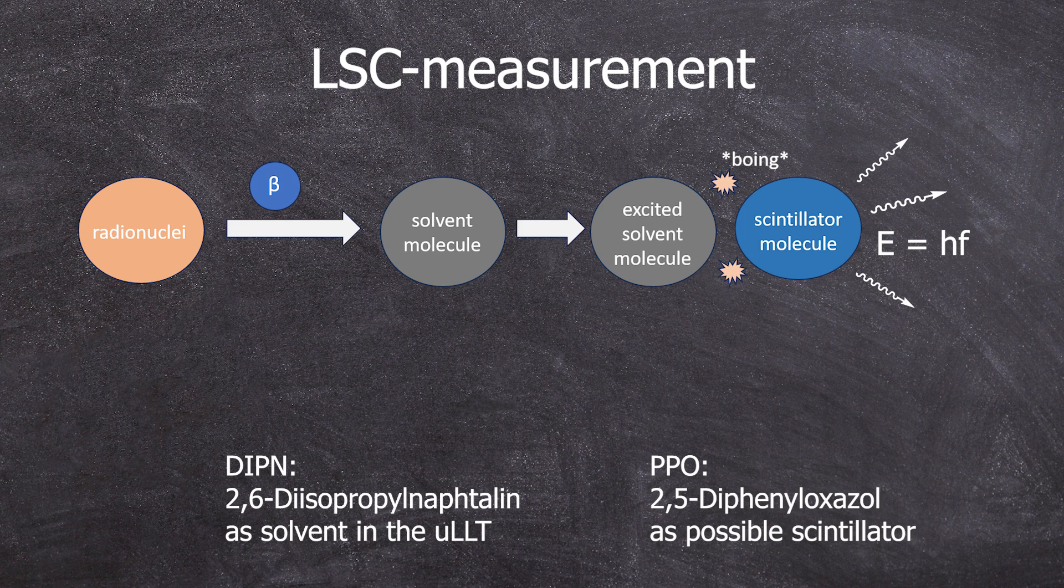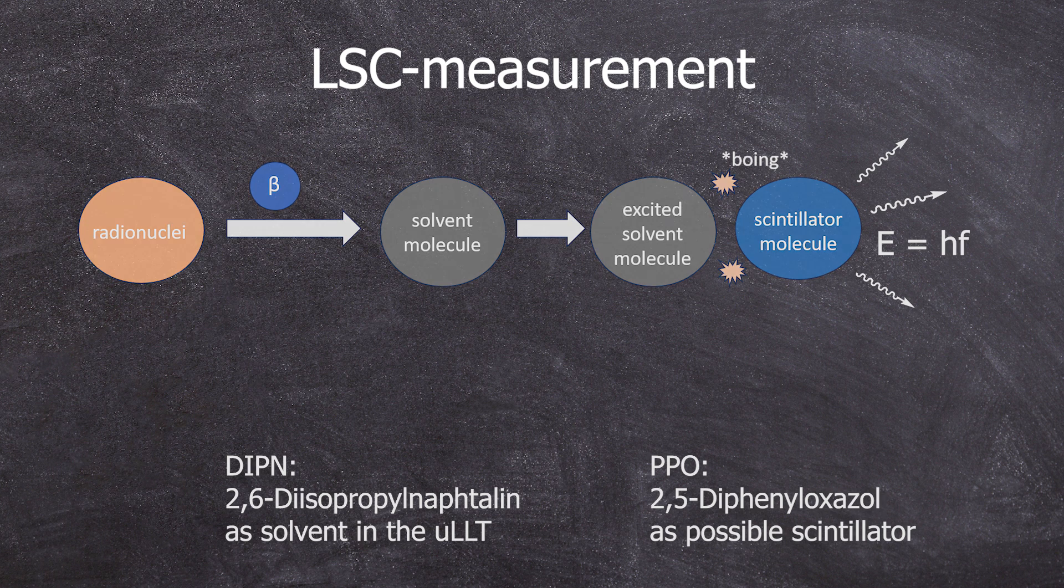However, the scintillator can also be excited simply by light and then fluoresce. No matter how weak this fluorescence is, it would distort our measurement results, so we have to wait until this light-induced excitation subsides and the scintillator is only excited indirectly by radioactive decay in our sample.